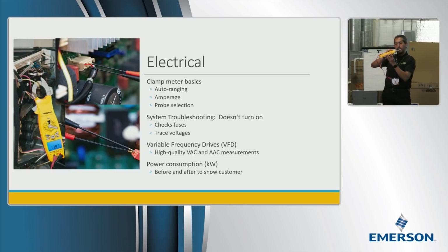Absolutely. On the side, there's an inrush button. You put it on the amps feature, just press inrush, put it on the wire before you fire up the system, and it captures that peak amperage for you. Good question.